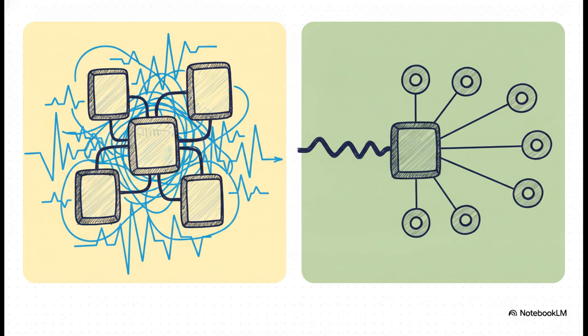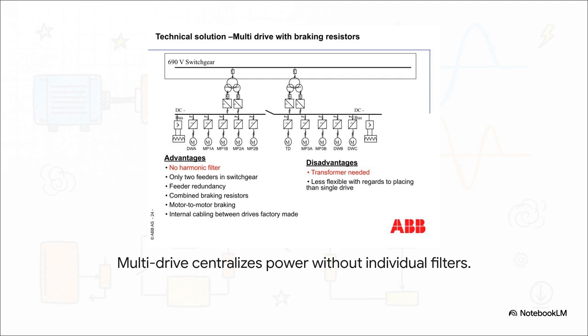But a multi-drive system, that's where it gets elegant. It uses one massive common rectifier to feed a shared DC bus, so you're filtering that distortion just once, centrally, right at the source. And looking at the setup, because we have that central common supply unit feeding the shared DC bus, you'll notice there are no individual harmonic filters hanging off every single motor drive like your mud pumps or your top drive. You filter it once at the common rectifier, and it's effectively eliminated for every inverter downstream on that shared bus. Plus, this shared DC bus lets you do some really incredible things, like motor-to-motor braking. You can use one combined braking resistor bank for the entire network instead of sizing heavy individual resistors for every single motor. It is incredibly efficient.